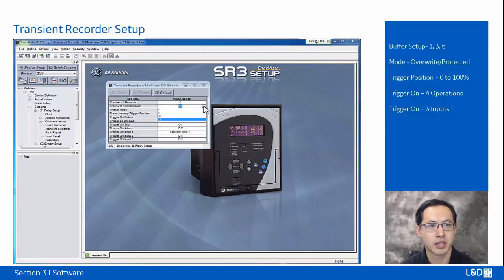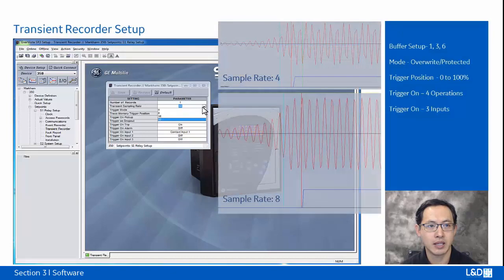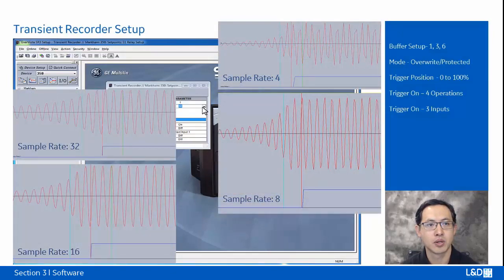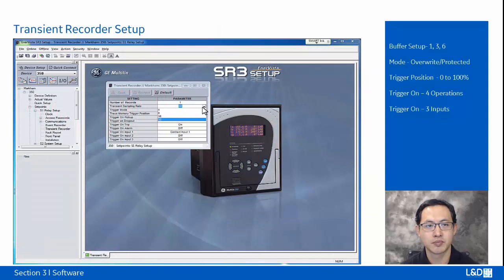And for sample rate, we can pick 4, 8, 16, or 32. So if you have a higher sample rate, you have a better resolution of the waveform, and then a shorter waveform can be captured. In the trigger mode, we have overwrite and protected. If it's protected, that means the waveform will be saved up to a certain amount and then stop. If it's overwrite, that means the new waveform will always overwrite old waveforms.